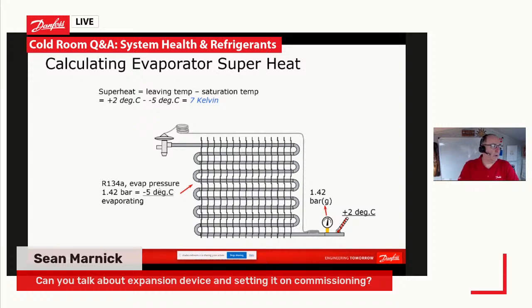In this example, we are evaporating with 134A. Our evaporator pressure is 1.4 bar, which gives us -5 degrees C. So we would do that on the old refrigerant slider device. We used to clean the ice off the windscreens when I was much younger with those in the winter time. But yes, we use our refrigerant slider, and then we work out with that particular pressure on that particular refrigerant. So 134A at 1.42 bar, and that is -5 evaporating.